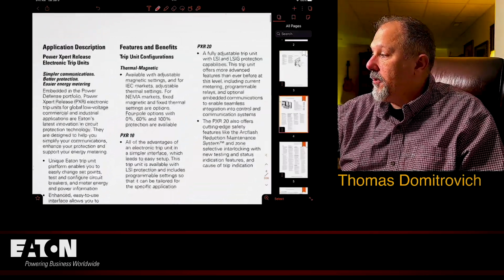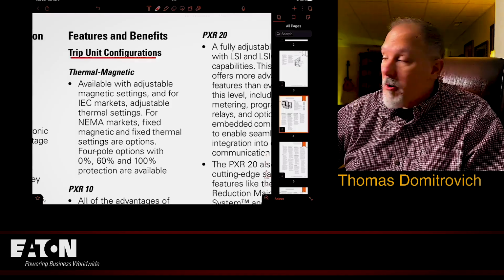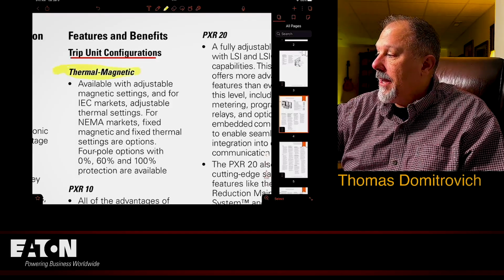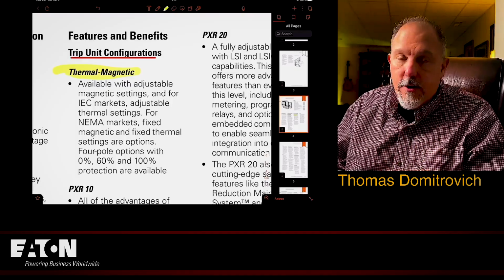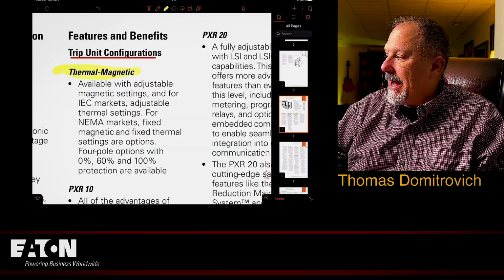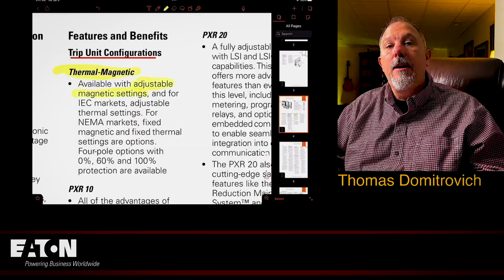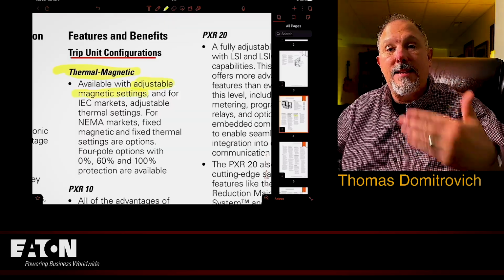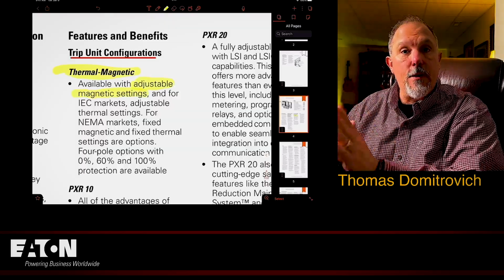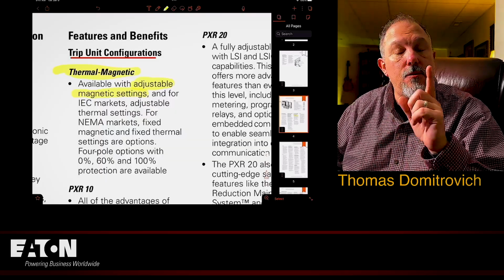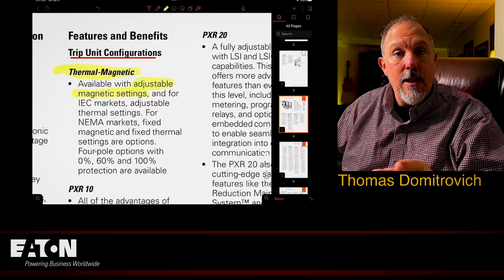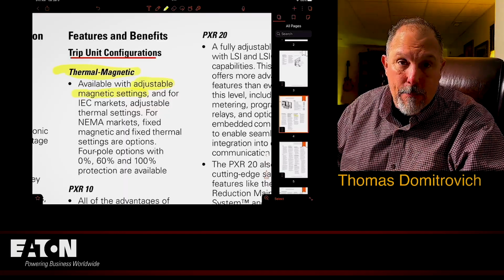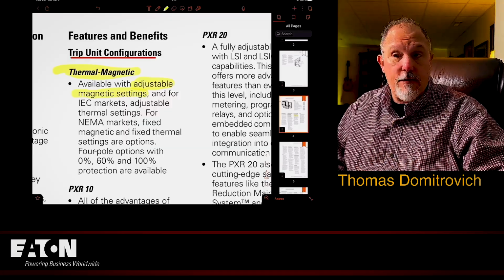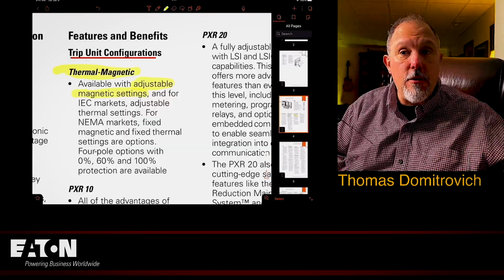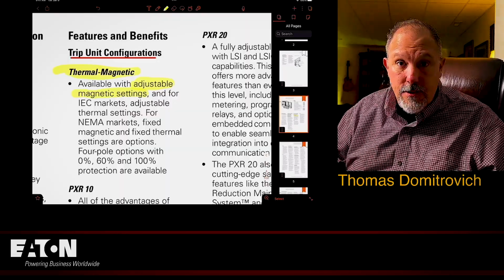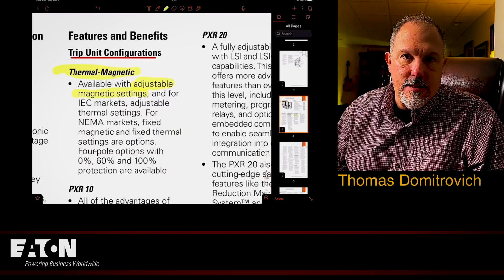If I look at trip units or trip unit configurations, we have the thermomagnetic. That is your base unit. With thermomagnetic only circuit breakers, you're not going to find an arc reduction maintenance switch. You'll notice that it has an adjustable magnetic setting. When you hear adjustable magnetic, you're hearing the adjustable instantaneous. That is the portion of the trip curve for very high fault currents that commands the device to respond without an intentional delay. But the fault currents have to be high enough to get that to happen. That's the challenge with an arc flash. When you have an arc flash event, if your fault currents are low enough, your arcing currents aren't in that magnetic region, and hence you'll have a longer delay time, and hence you'll have higher incident energy.